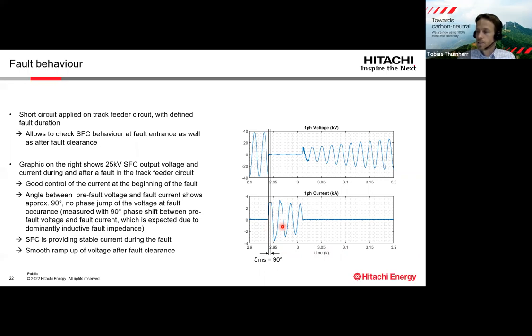As I've mentioned, it's very important that the SFC doesn't introduce a jump in the voltage at the beginning of the fault or during the fault. It's a little bit difficult to show that on the measurements because the fault impedance is so low and there is virtually no voltage remaining.